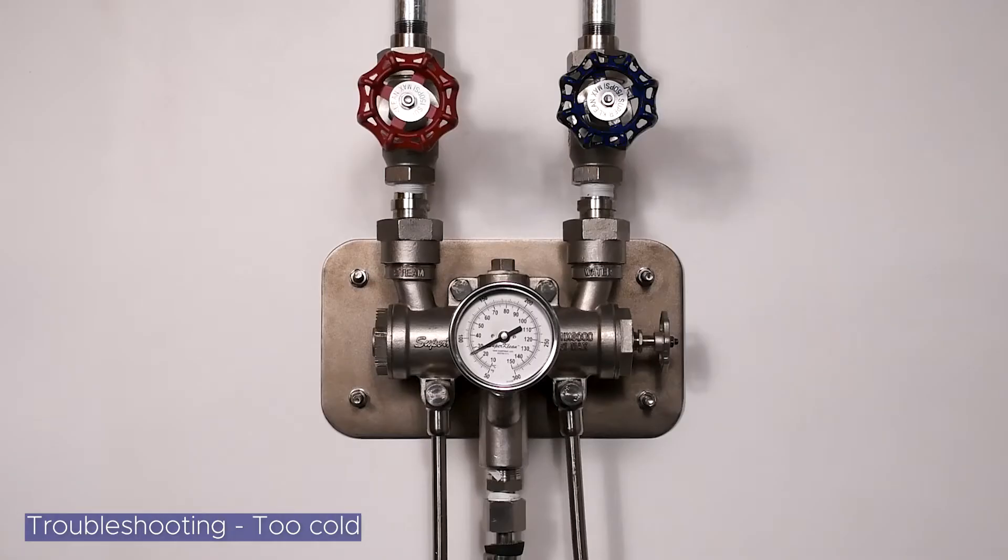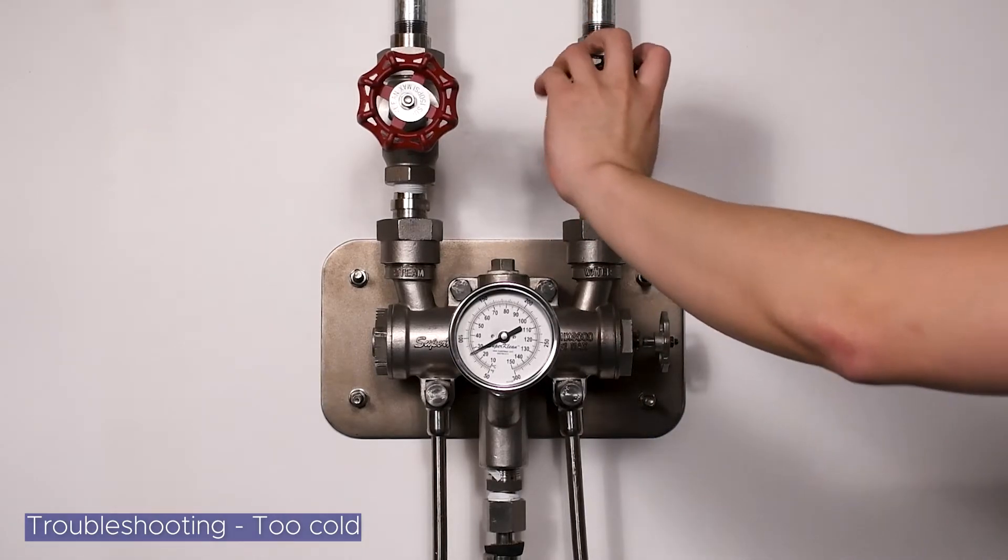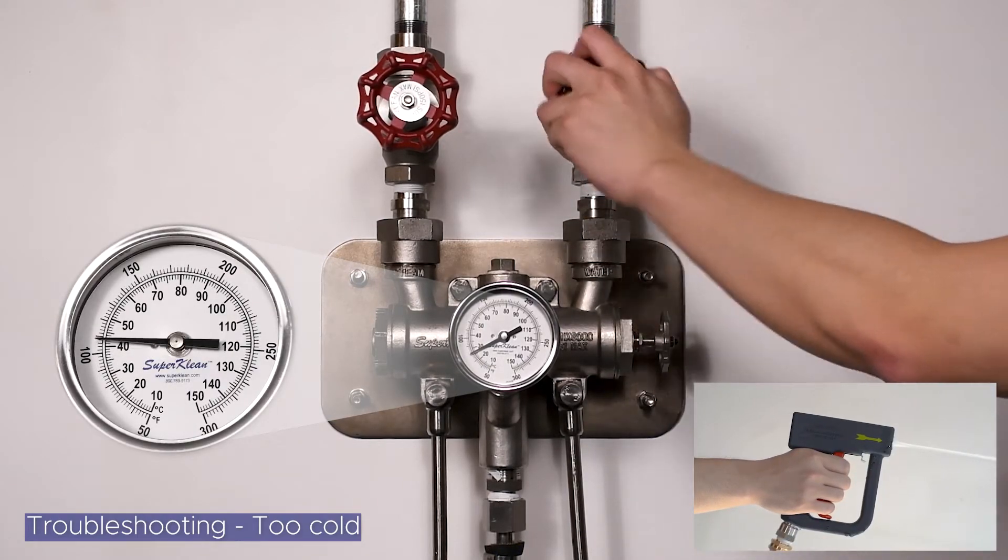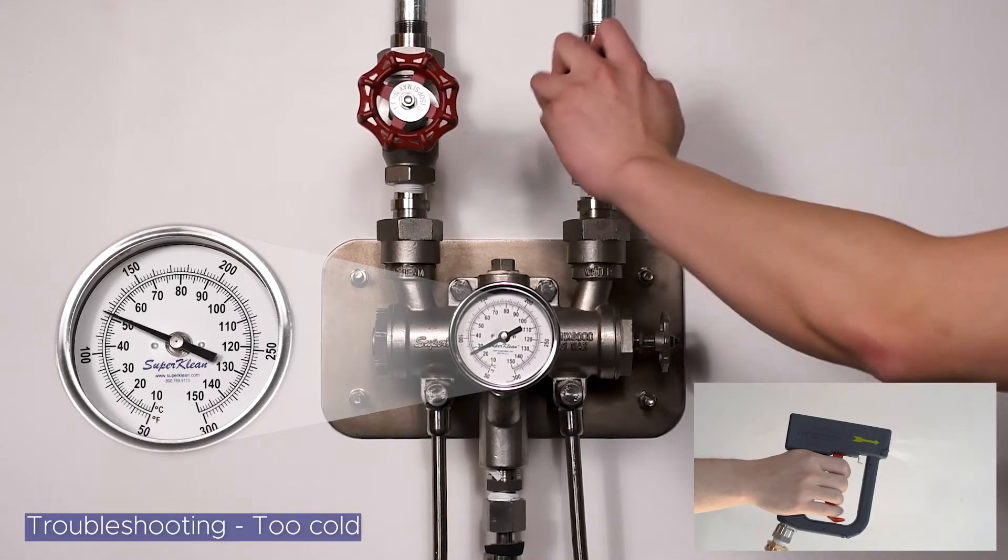In the case that the temperature output is still too cold after fully turning the temperature adjustment hand wheel clockwise, begin to decrease the cold water flow by closing the cold water globe valve by slowly turning it clockwise while spraying the nozzle. Continue turning until the temperature output stabilizes at your desired temperature.